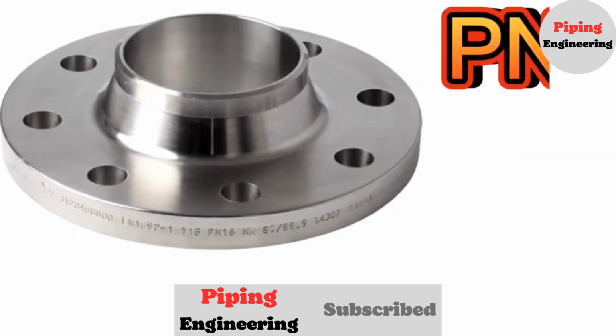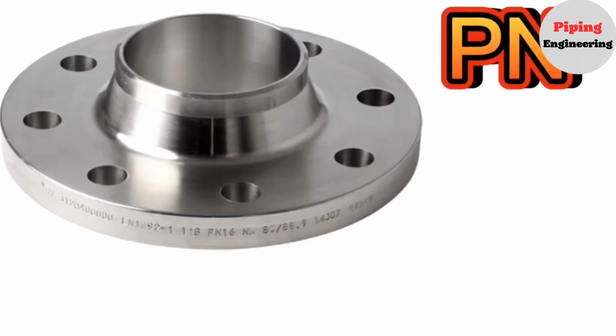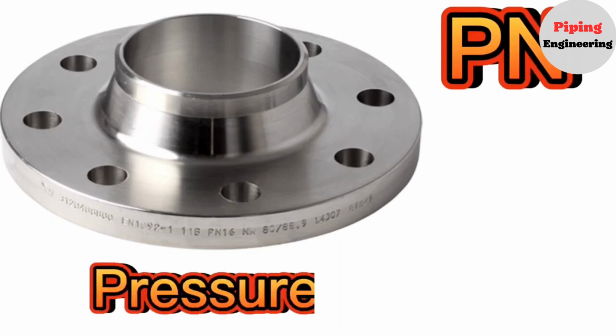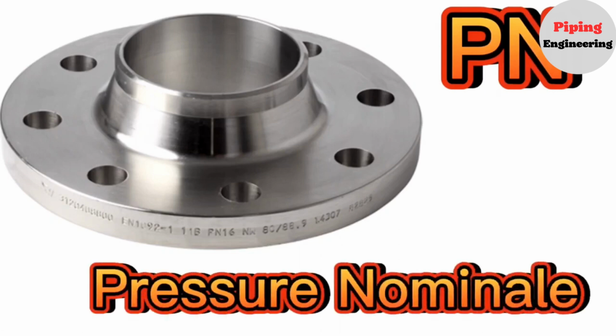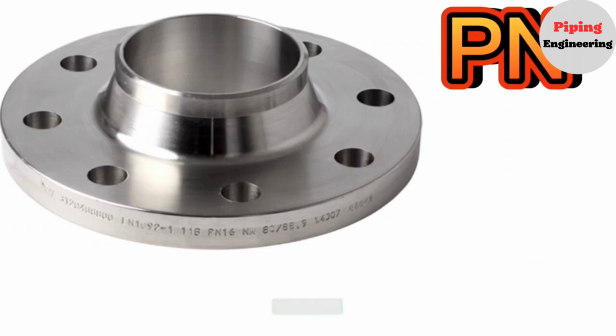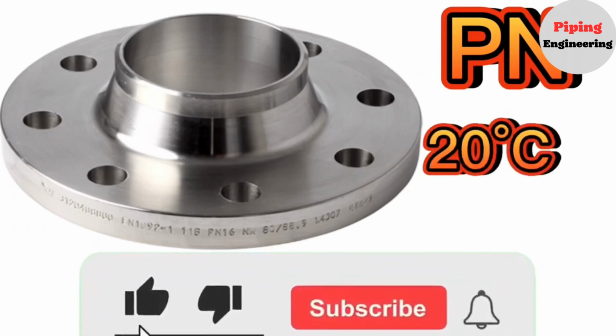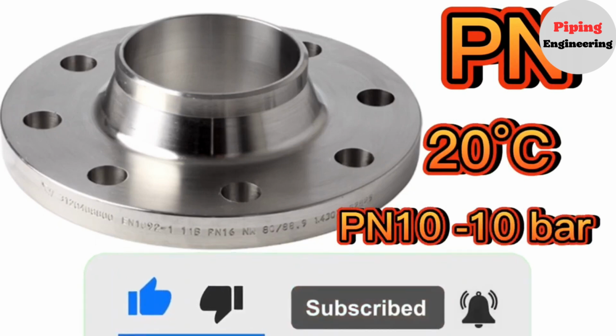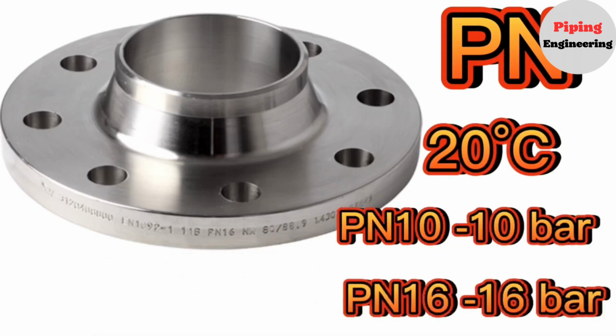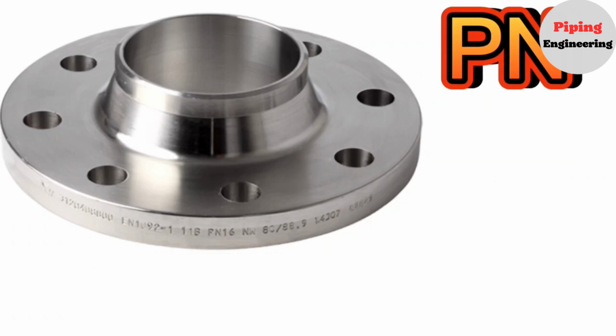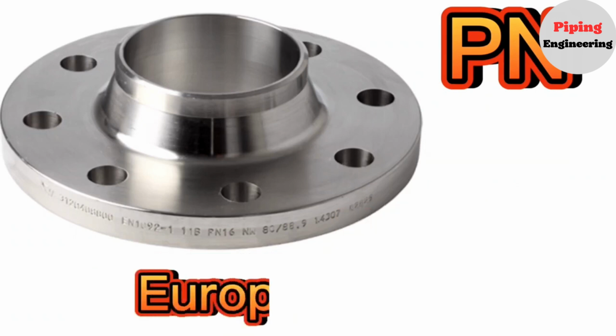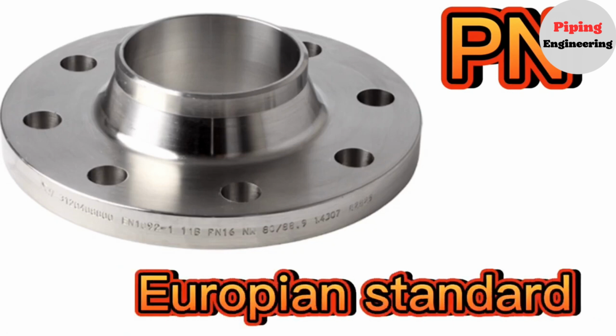PN types of weld neck flanges are also used in fabrication. PN stands for pression nominale. The numerical value written after PN specifies the flange's maximum applicable pressure in bar, at a reference temperature of 20 degrees Celsius. For example, the cold working pressure of PN10 flanges roughly equates to 10 bar, PN16 to 16 bar and so on. Simply said, it's a classification system for flanges mostly used in European standards for installations in European countries.